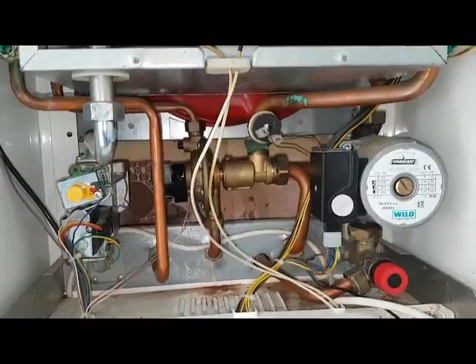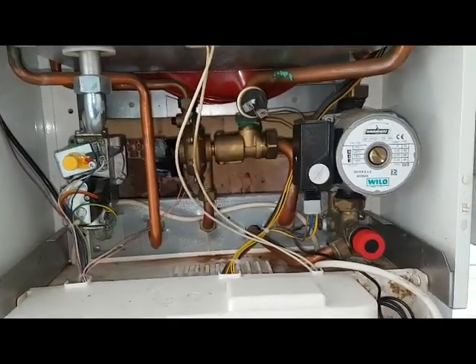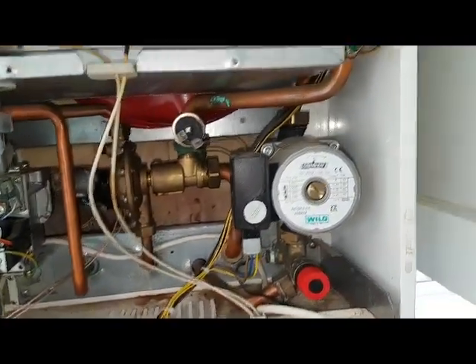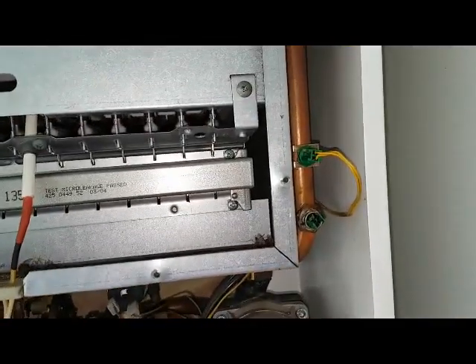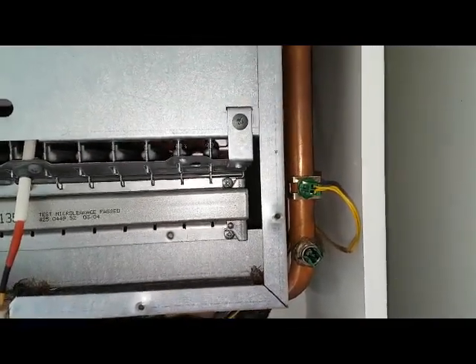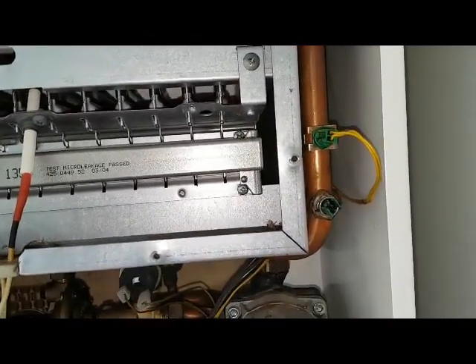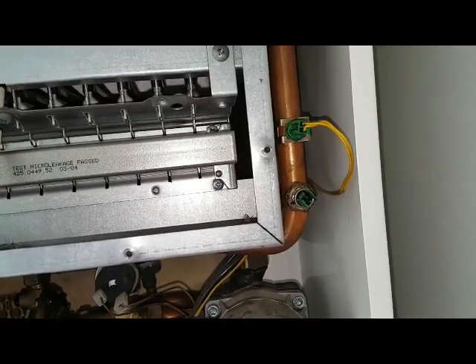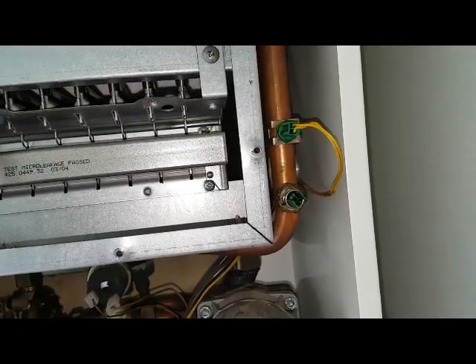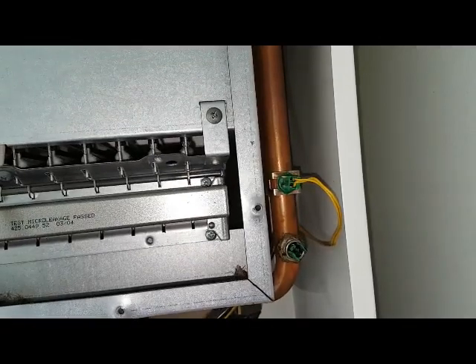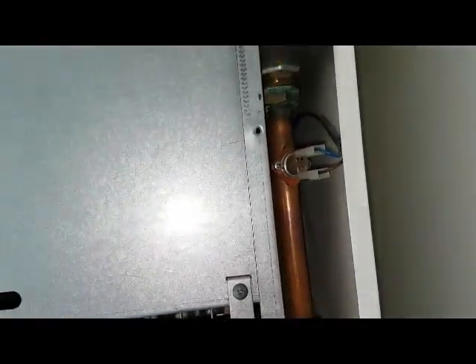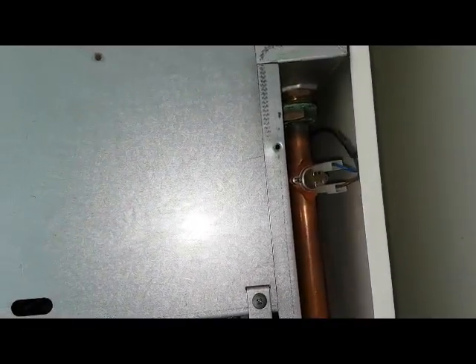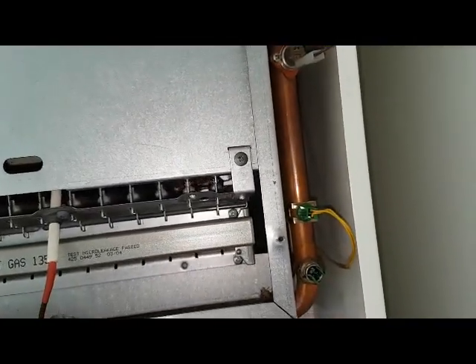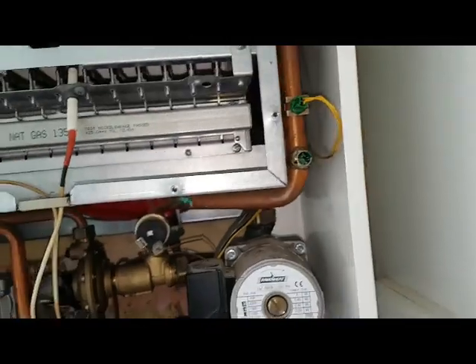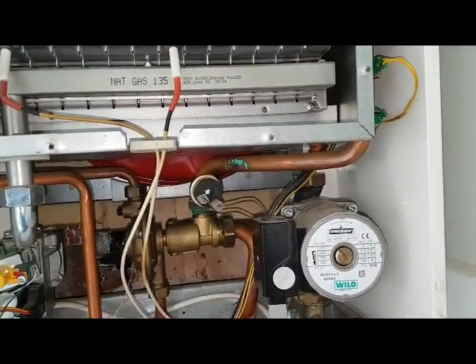Now for the controls of the central heating, what you've got is the central heating thermistor, which is an external one we fitted, that's the internal one. We were having a lot of problems with this, so we fitted an external one, as you can see. You've got the overheat thermostat, so the thermistor must be calling. Once that does all of that, then you can have the pump running.